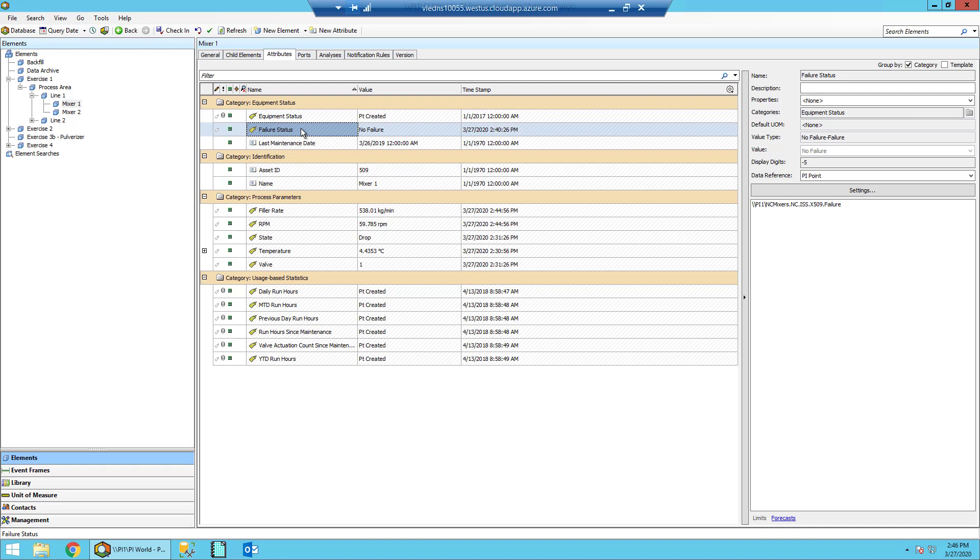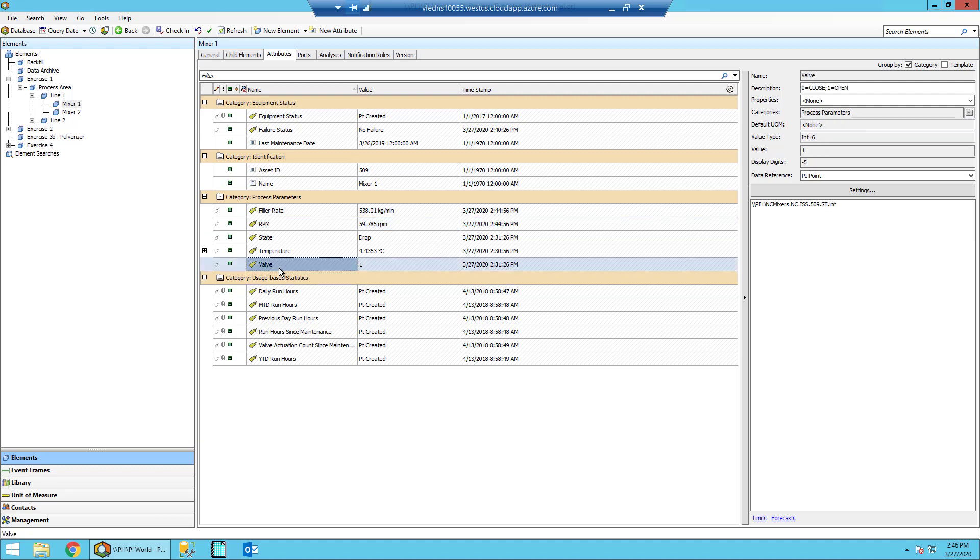I also want you to note that there is an RPM value here. So each mixer, if it's running, should have positive RPM. And there's also a Valve attribute here. So when we're calculating if the mixer is running, we'll be looking for positive RPM as well as the Valve being open. And we'll also want to make sure that there's no Failure State going on.